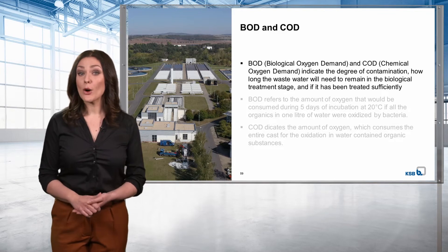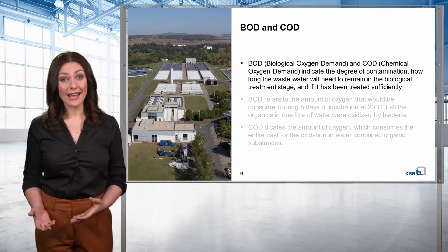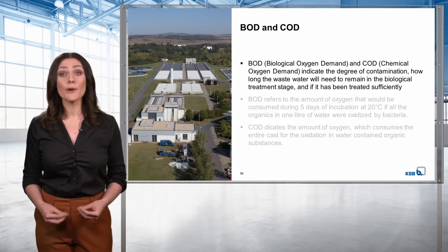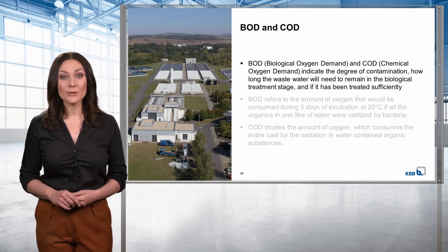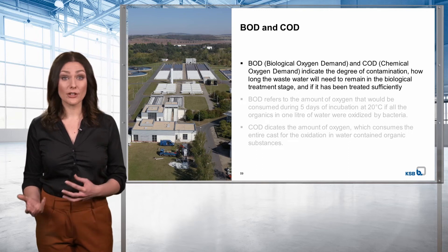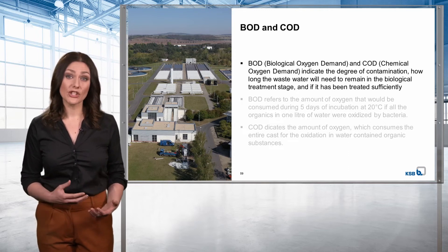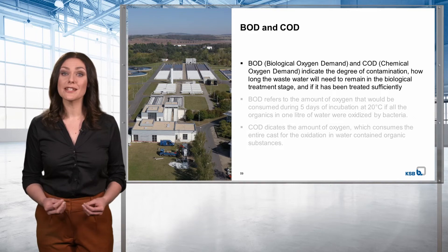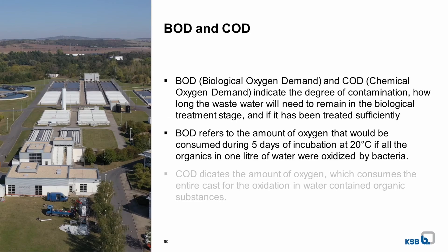This is where the reference values BOD and COD come into play. BOD stands for biological oxygen demand, and COD for chemical oxygen demand. These values indicate the degree of contamination, how long the wastewater will need to remain in the biological treatment stage, and if it has been treated sufficiently. In principle, BOD and COD are two key values for selecting a treatment plant. The BOD refers to the amount of oxygen that would be consumed during 5 days of incubation at 20 degrees Celsius, in order for the bacteria to oxidize all organic substances in a litre of water.